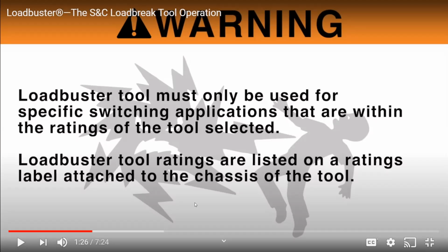So if you take a reading with an amp meter and it says 310 amps, can I use a 200 amp load buster tool on it? No, obviously not. It's going to blow up the tool. So definitely read the ratings on the tool before you use it.